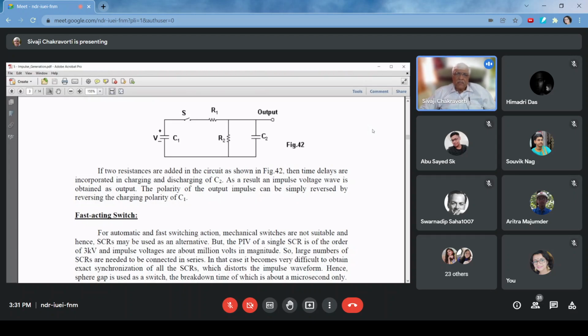The big question always is about this switch S. Please remember that we are not talking about 1 volt, 20 volt, 100 volt. We are talking about 100 kV, 200 kV. Initially, when C1 is fully charged, let's say up to 100 kV, and S is open, then the left-hand side of switch S is connected to a 100 kV source, but the right-hand side is at 0 volt because C2 is not charged. So this switch has to withstand 100 kV under open condition, and then it has to close the circuit very, very quickly because for the lightning impulse itself, the front time is only 1.2 microseconds. So if the switch cannot close the circuit very fast, then you will never get the wave front properly.